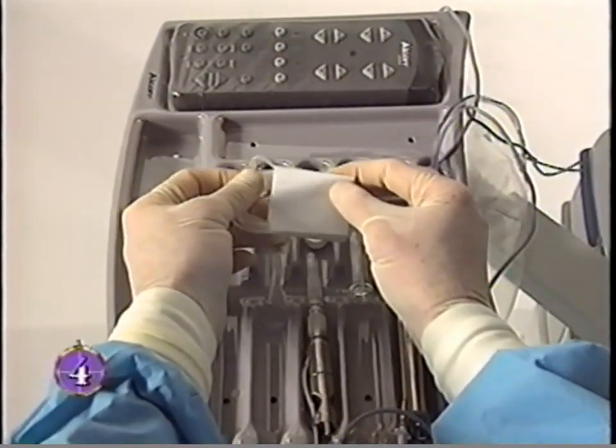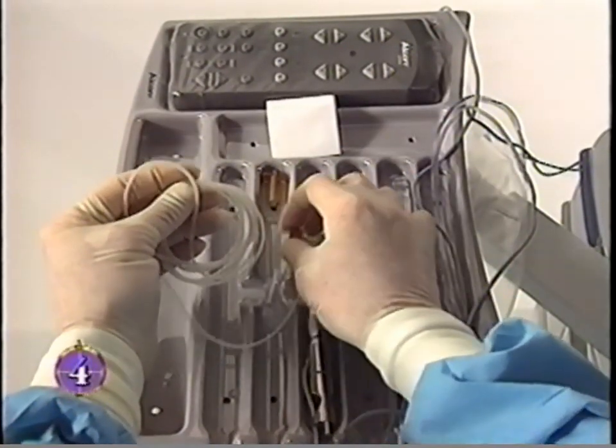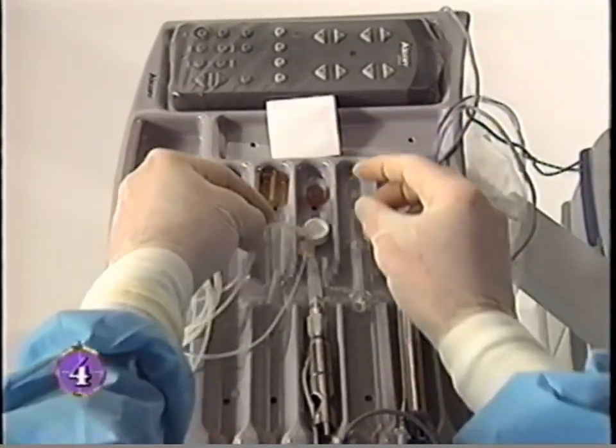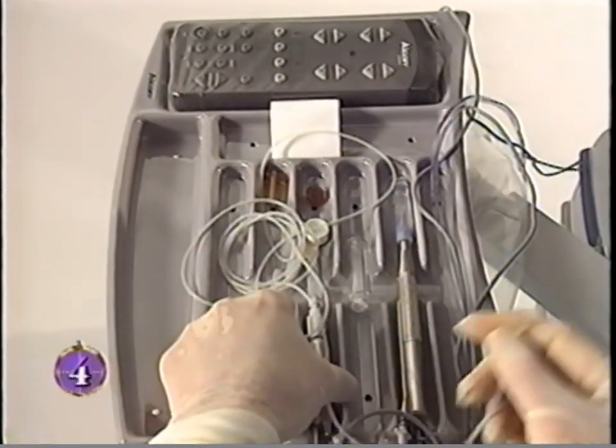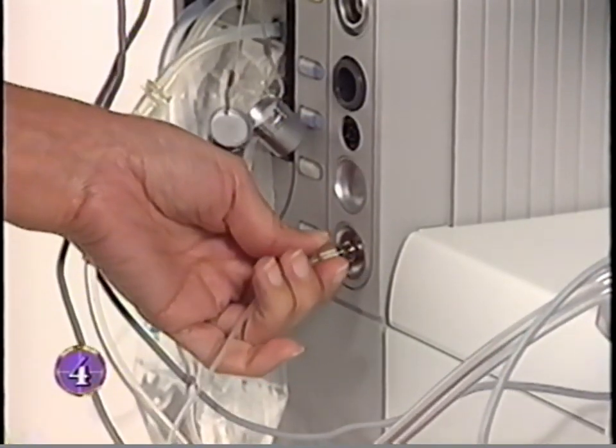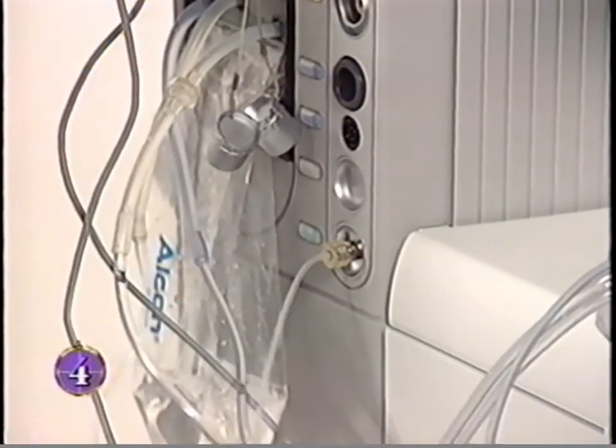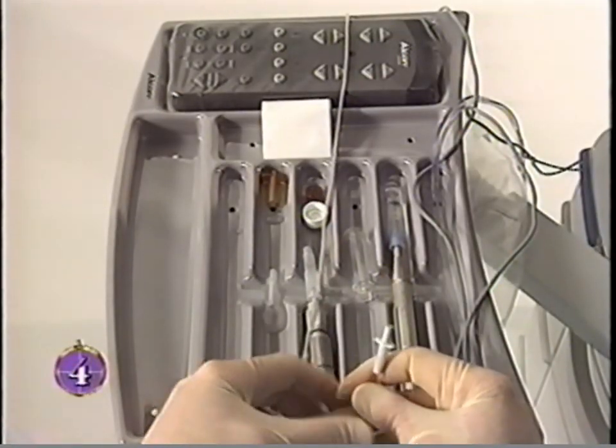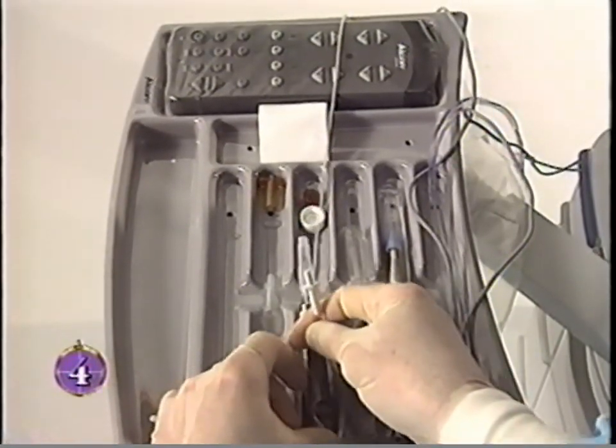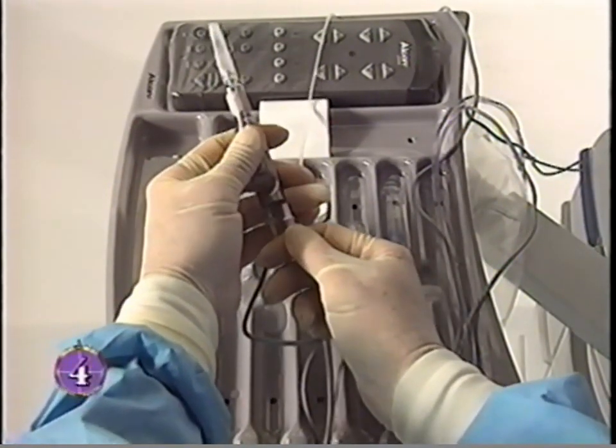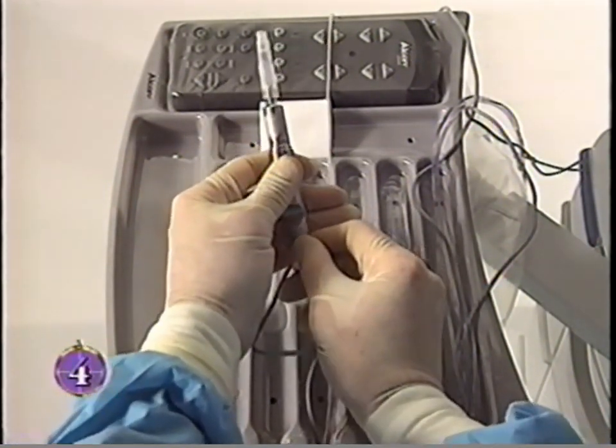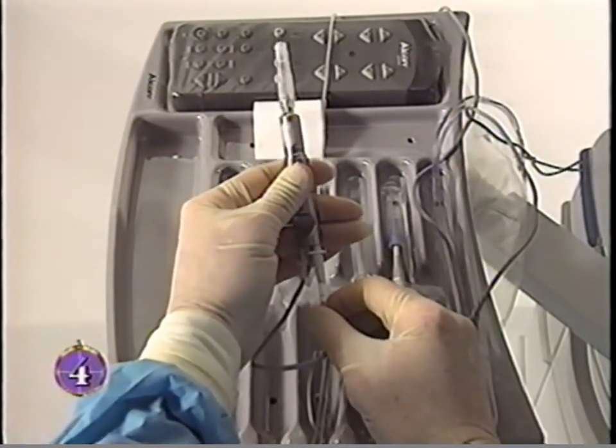Connect the tubing to the injector, then hand off the end with the male twist lock luer to the circulator. Connect that luer to the system VIT port on the side panel and disconnect the irrigation tubing from the ultrasound handpiece. After separating the fluidics line back 2 feet, connect the irrigation tubing to the injector.